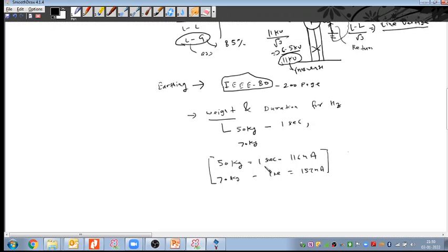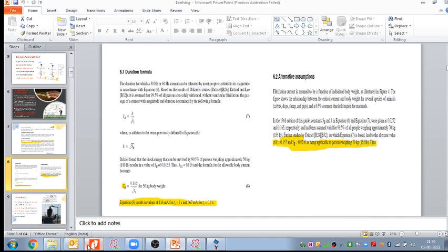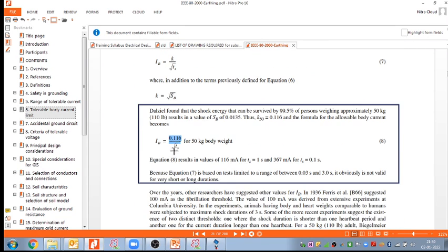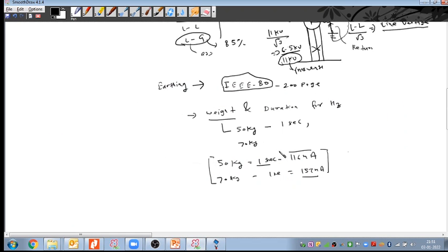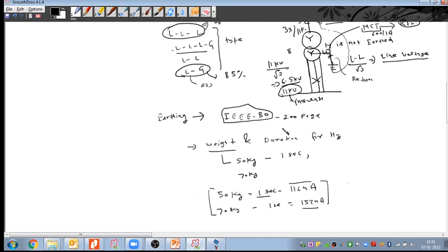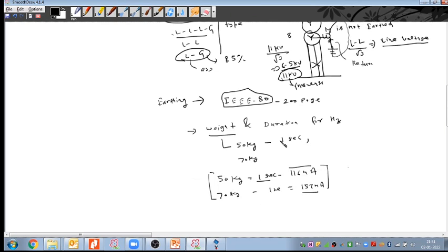Based on that formula, you can calculate what the tolerable current should be if the time is 0.5 seconds. It is the same formula that we have seen in this IEEE, with the square root of t_s, so in place of 1, you can put 0.5. You can calculate the tolerable body current for different time durations also. Hope this point is clear: how much current a person of 50 kg or 70 kg can tolerate for 1 second, and how it depends on different time durations. If clear, please let me know so that I can move to the next topic.